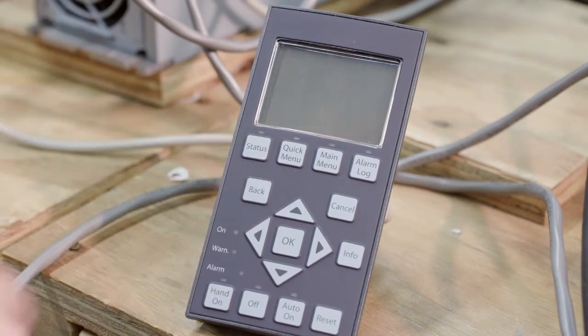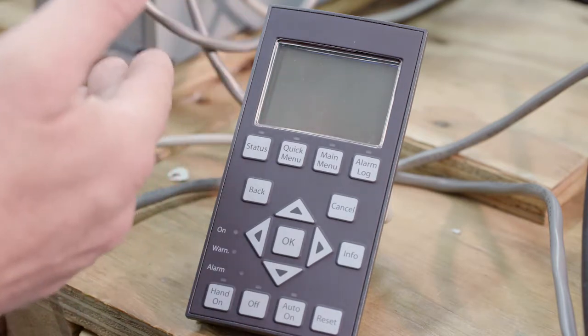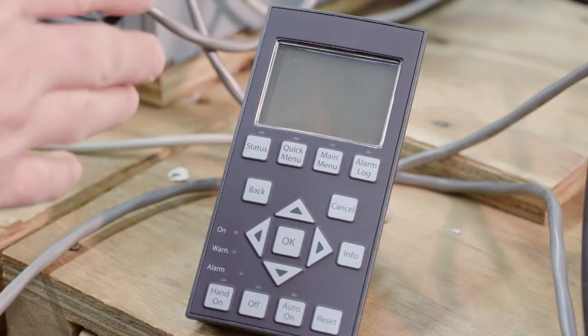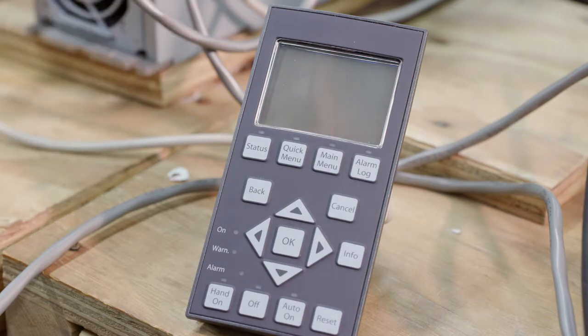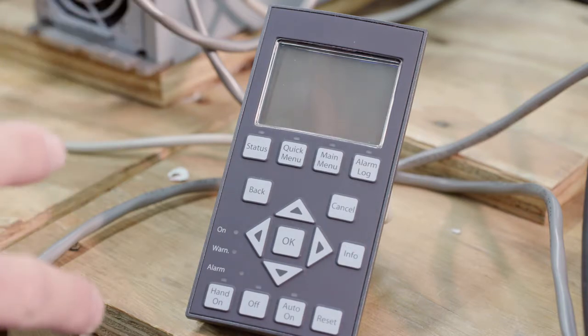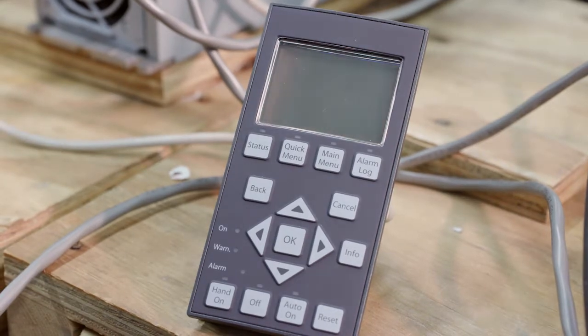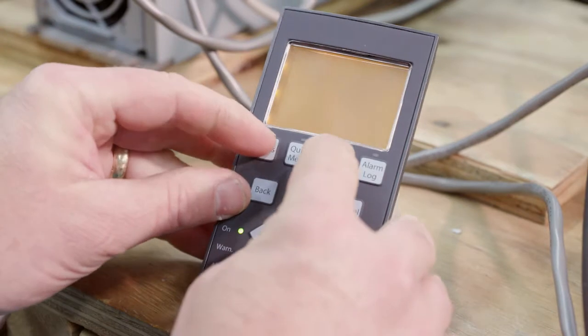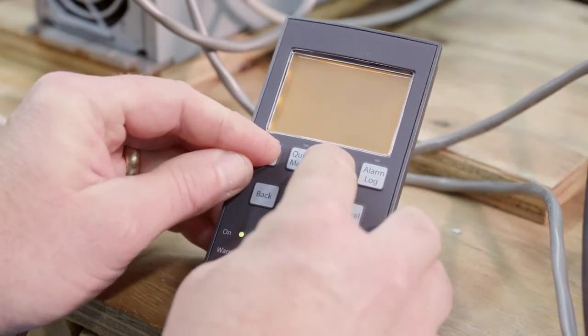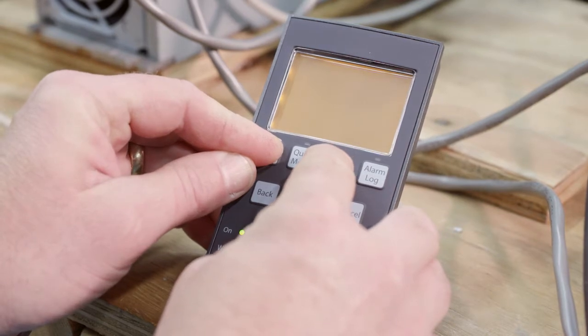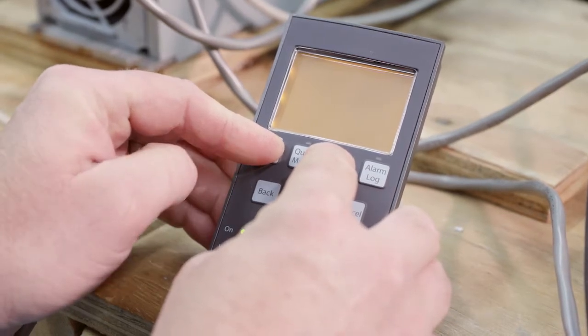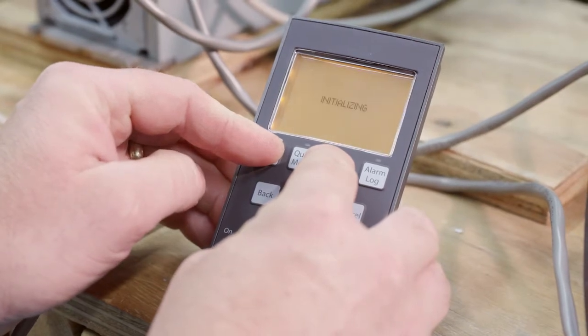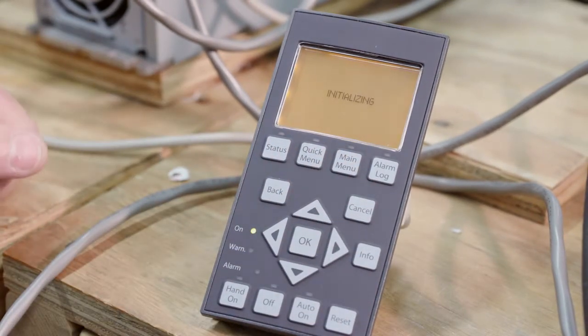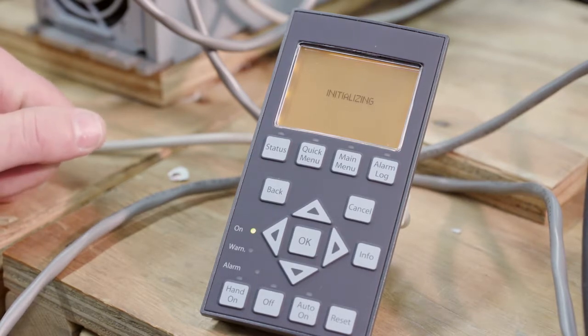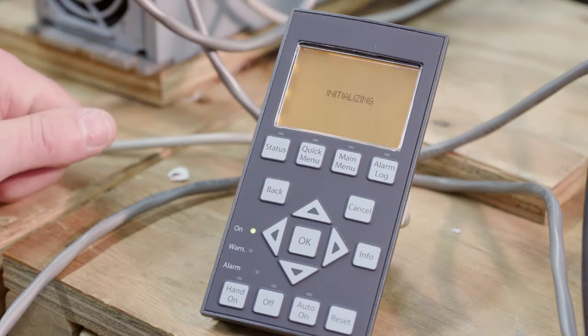The other way to do it is through your parameters. Obviously, it has to be powered up at the time, and you go to 1420, and you can do it that way. So we're going to use the three-finger reset method in this case. So I'm going to press status, main, and OK, and hold those down until I see the word initializing. Now I can let go. So now I've just reset everything to the factory default settings. So you will not have to do this if it's a brand new unit from the factory.